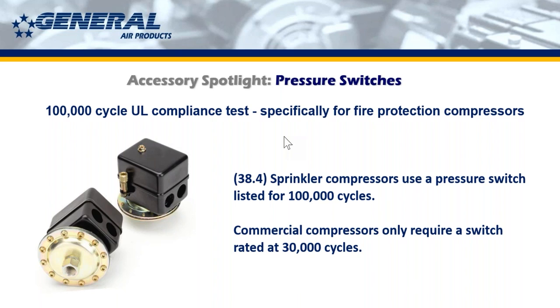But I wanted to let you know that they're coming, and why we didn't just jump on the bandwagon. Again, I understand the convenience of it, but to us, it's much more important that these things work properly and for a long time. And I don't want to see a compressor fail at 30,000 cycles, which most of the digital pressure switches that I know of on the market will fail at. Because we investigated using those, anywhere between 30 and 40,000 cycles is their max. That's why they're not UL listed as well. So something to keep an eye out for.